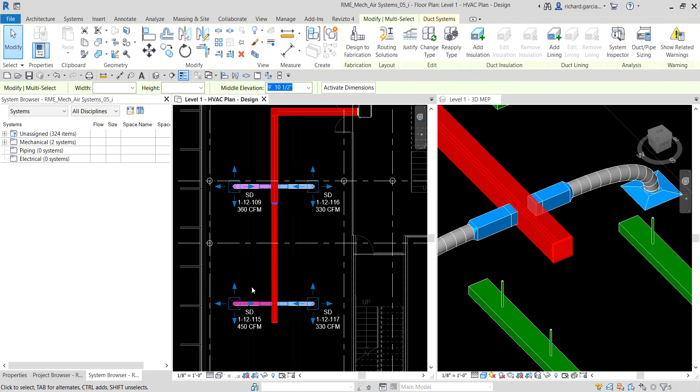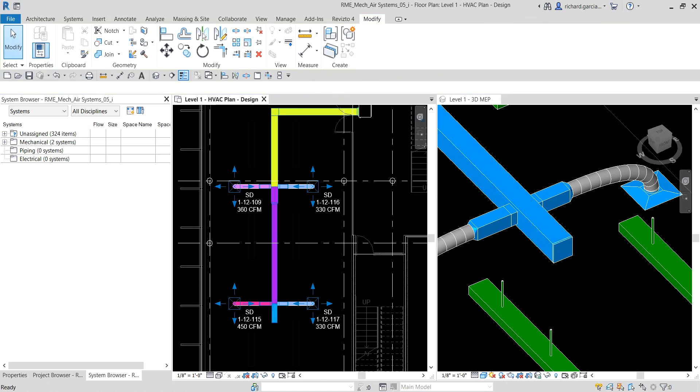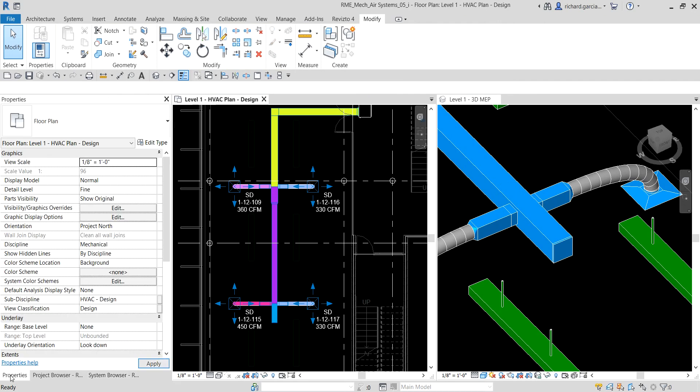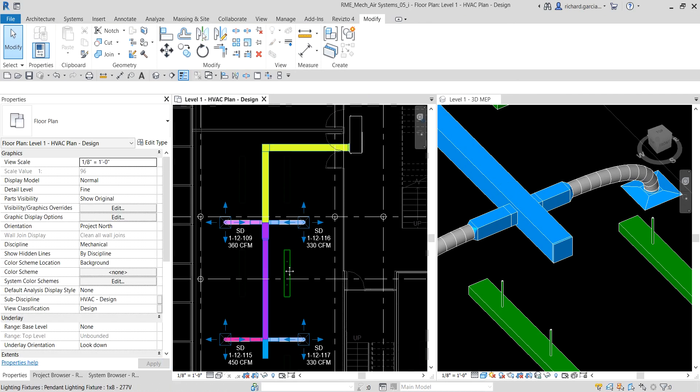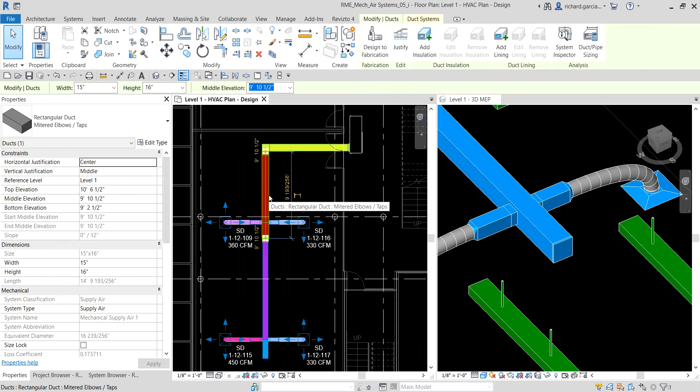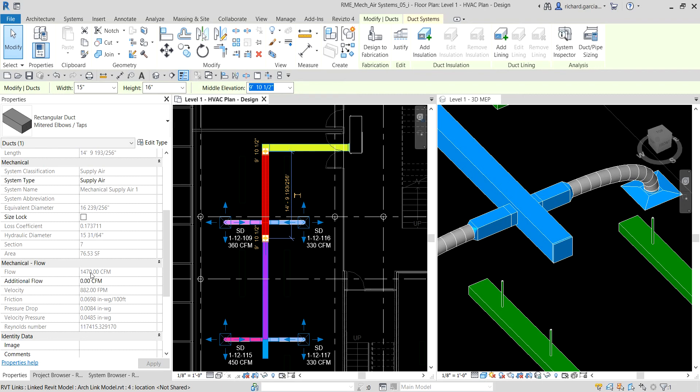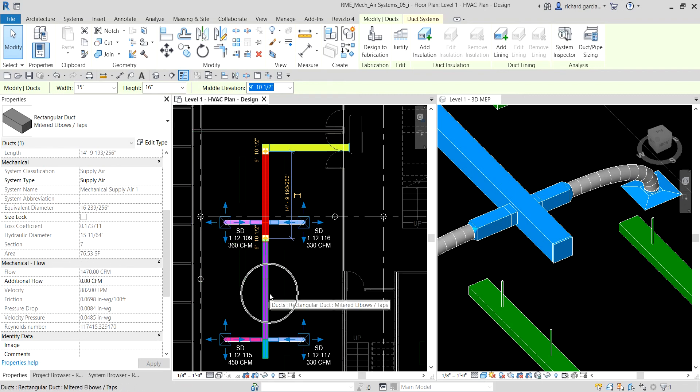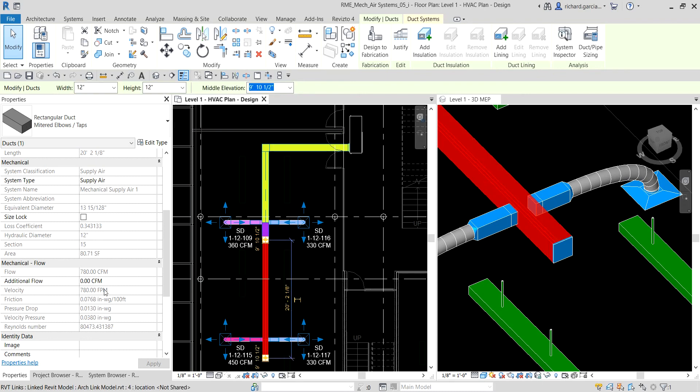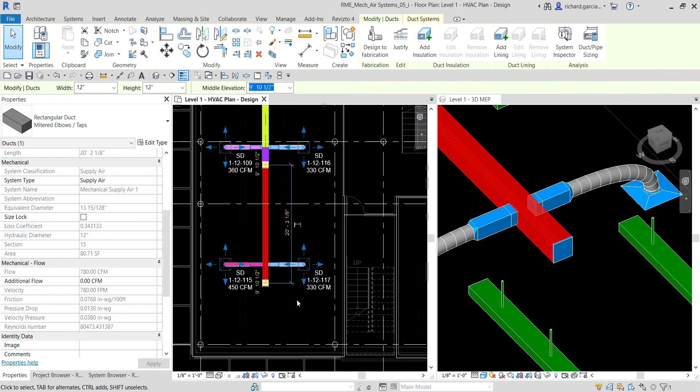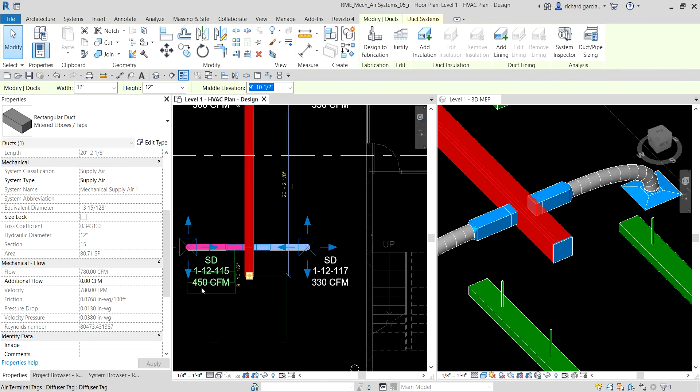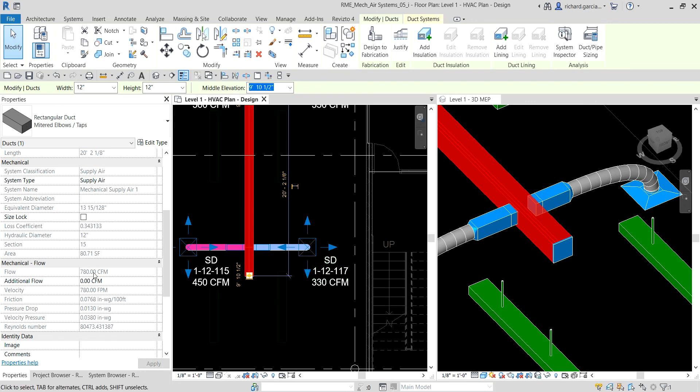You can verify the duct sizing by going to the properties. For this duct here, you can click that and verify the value here on our properties that shows you the flow. The total flow value is 1470 for that duct. If I select this duct, notice that the flow there is 780 because of these two here, so 450 plus 330 is 780.